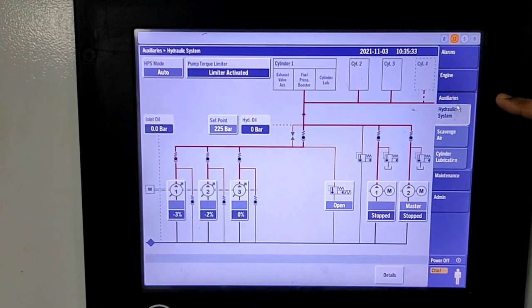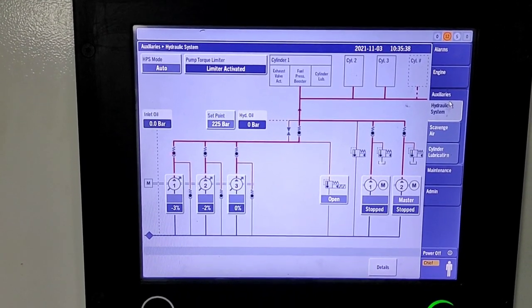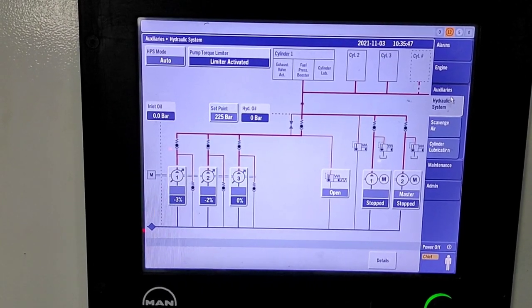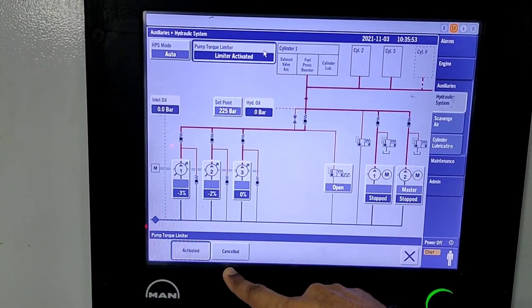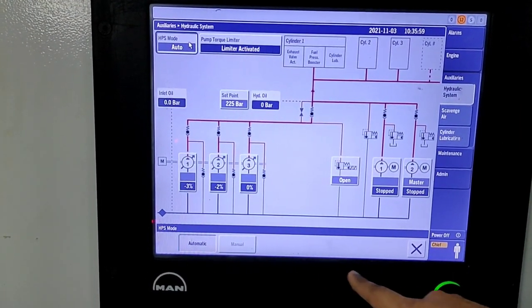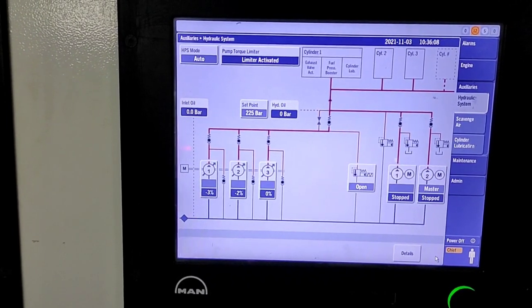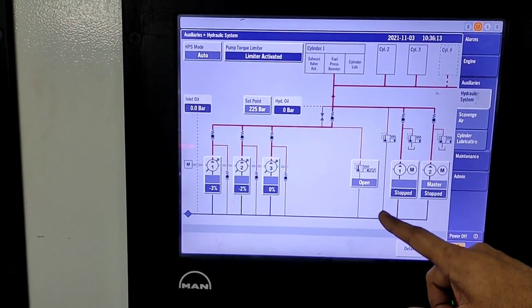In the hydraulic system, there is an HPS mode. In the HPS mode, on the left-hand side you can run auto mode or manual mode. Besides that, there is a pump torque limiter — you can touch and adjust it; two options come up: activate and cancel. You can also set the set pressure of the hydraulic oil — currently the set pressure is 225 bar. There is also a bypass valve you can adjust; every three months you should check that this valve is working properly.